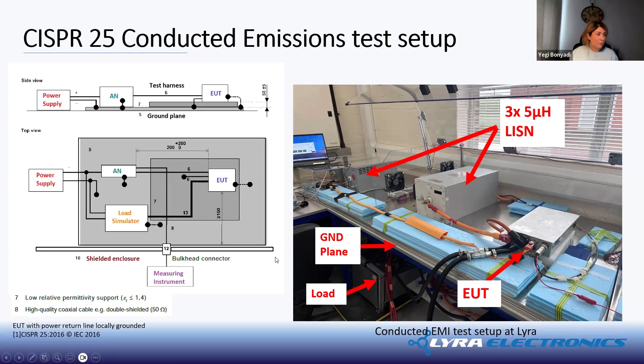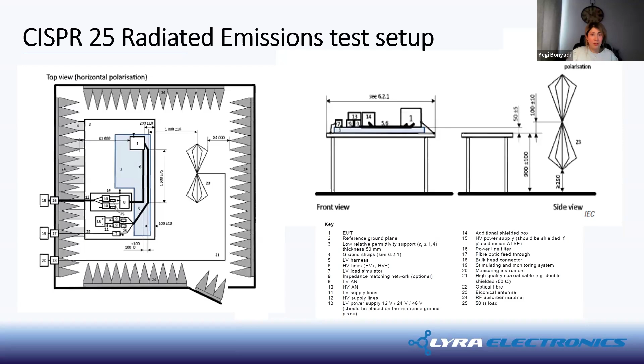The CISPR 25 standard also shows you the test setup that you need for radiated emissions. So again, it shows you how we need to place the antenna, what position the antenna should be, what the distance between the cables and the antenna is, and how the cables should run from the device all the way to your measurement. These are quite important to keep in mind. And if you're setting up your test in your lab, just make sure that you set them up according to these test standards.